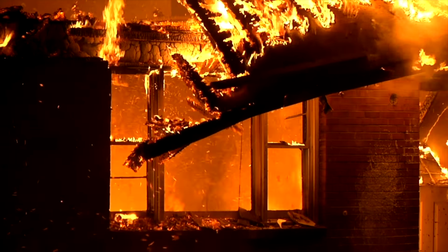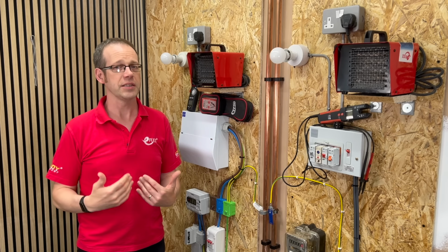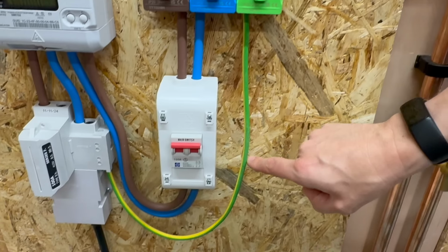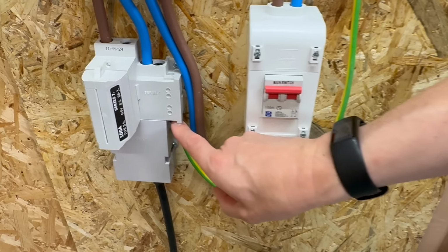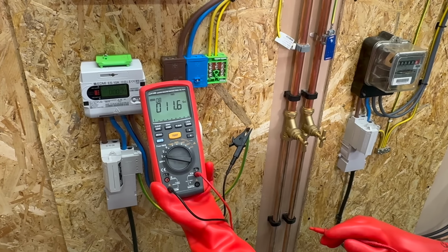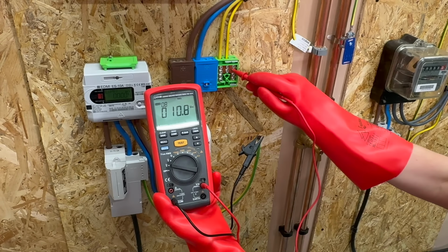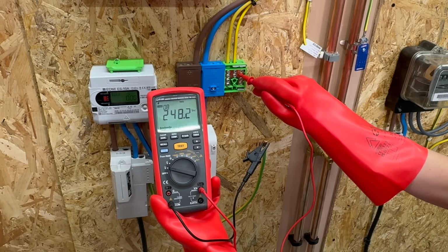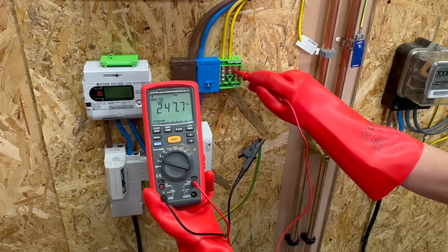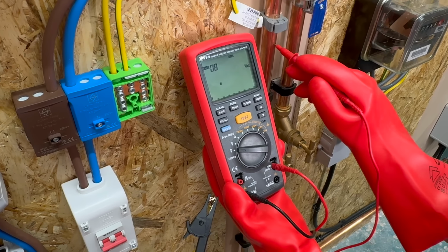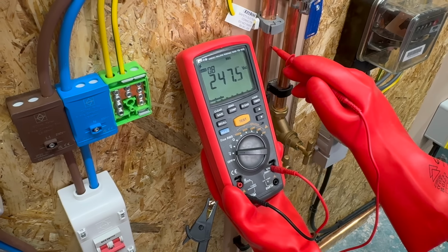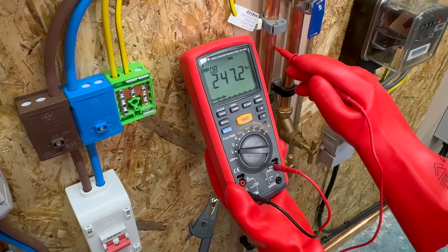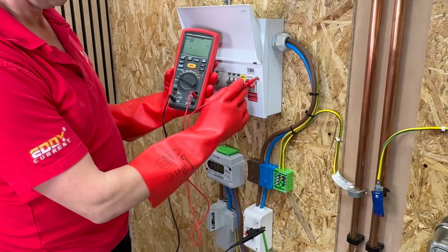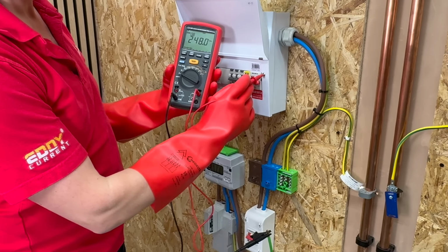The danger for anyone doing electrical work is that, much like myself at the start of the video, if I come along and disconnect this conductor to do some electrical work, then all of a sudden I'm handling a conductor that I might naturally assume is dead and safe to touch. But the reality is that this could be live at a high enough voltage to kill me. And it's not just the conductor or the earth bar that might be live at this voltage, it could also be the water pipe, the body of the consumer unit. In fact, anything that's connected to the earth terminal in one way or another.